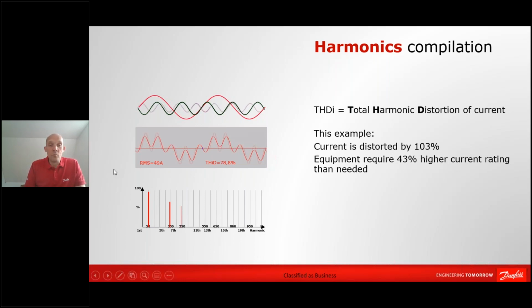Now I'll add a few more harmonics, or a few more signals, on top of it. Now I added the seventh harmonic, or the seventh order frequency. So 7 times 50 Hertz is 350 Hertz. When you add these three together, you have a curve looking like the one you have in the middle. You can see the RMS went up again and the THDI went up again. I add another frequency now, and you are almost seeing a representation of the green curve that you had to begin with from the frequency converter.